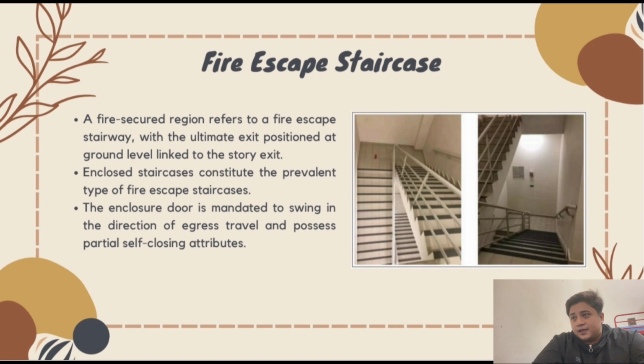Fire escape staircase. A fire secure region refers to a fire escape stairway with the ultimate exit positioned at ground level linked to the storey exit. Enclosed staircases constitute the prevalent type of fire escape staircase. The enclosure door is mandated to swing in the direction of egress travel, and possess partial self-closing attributes.